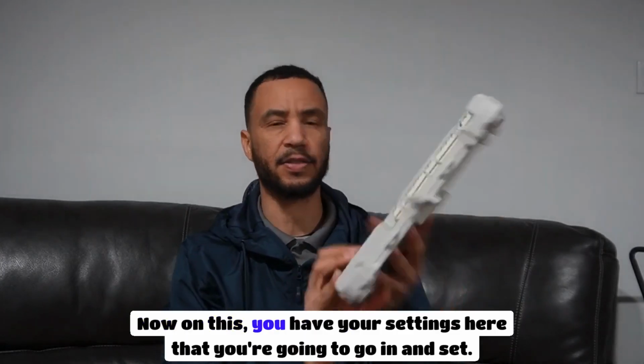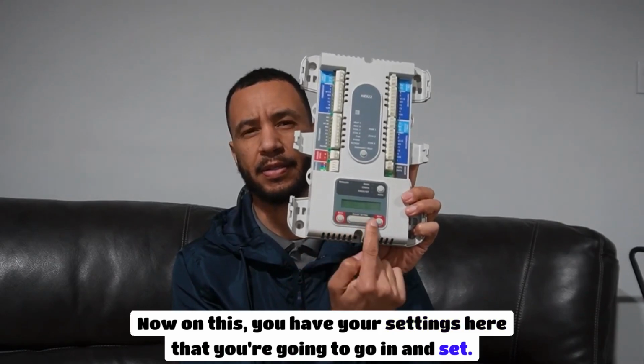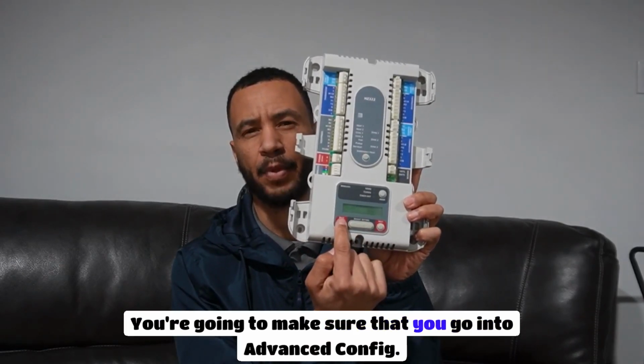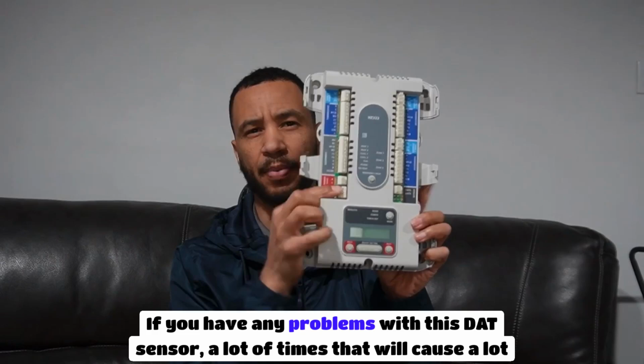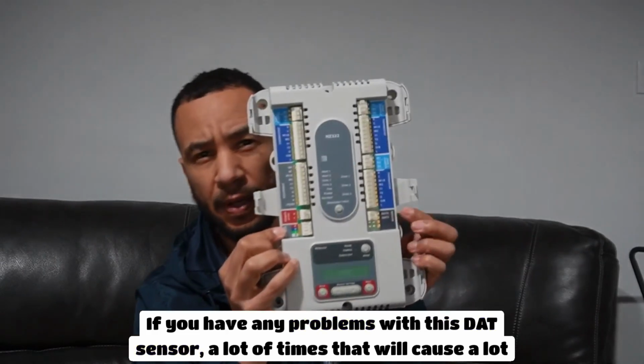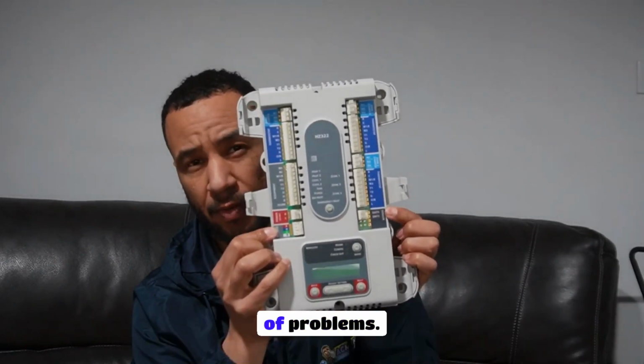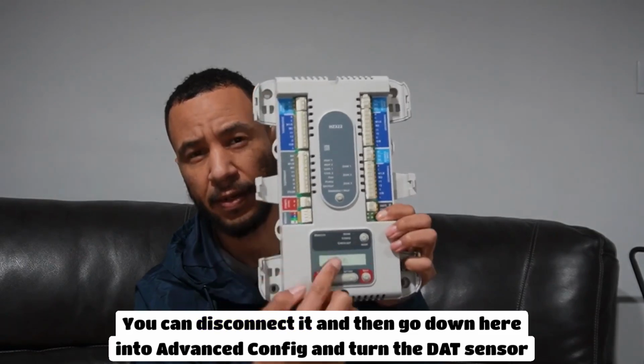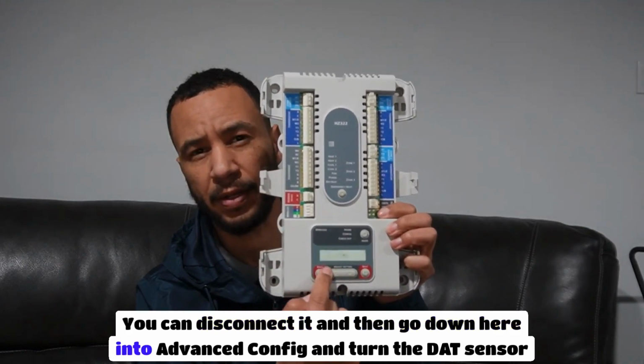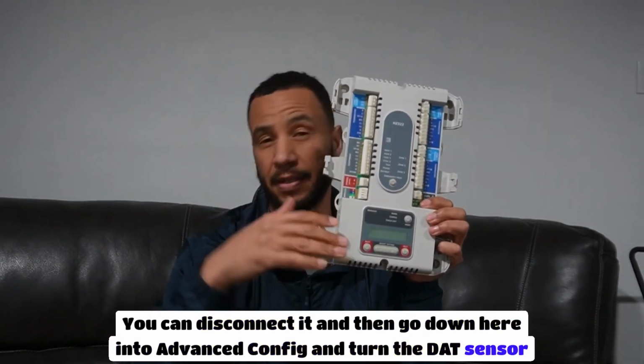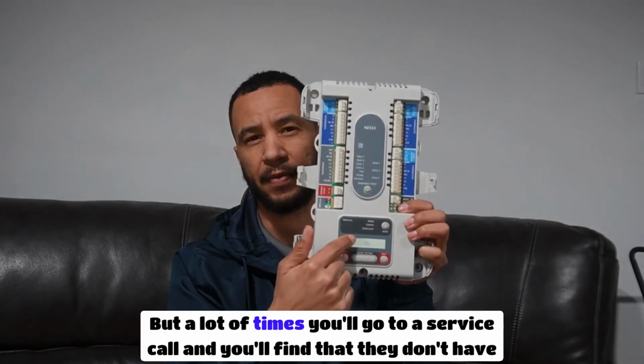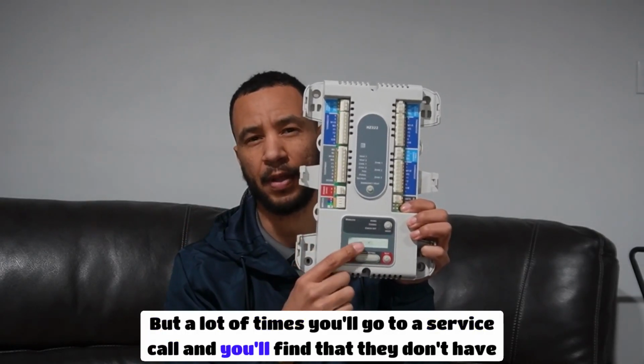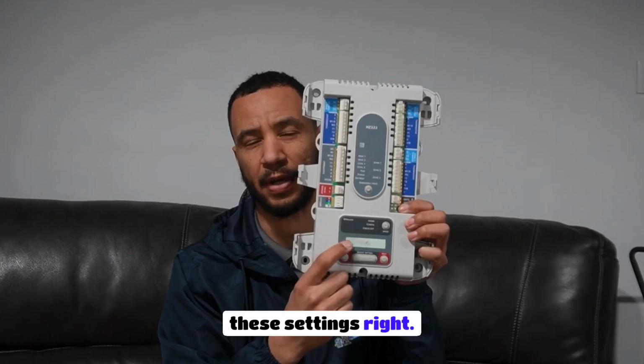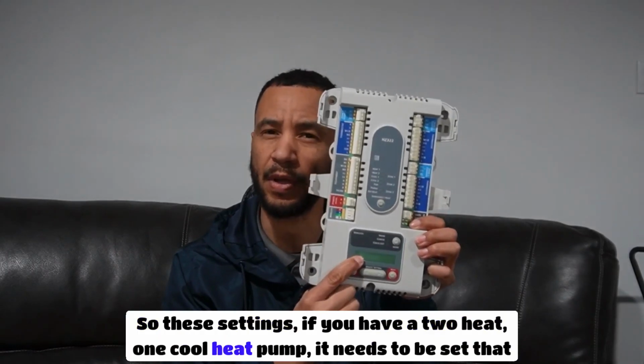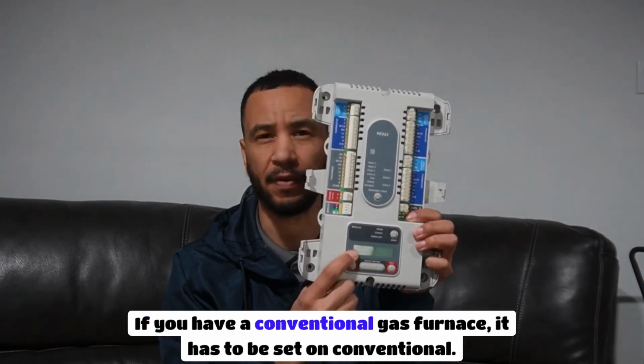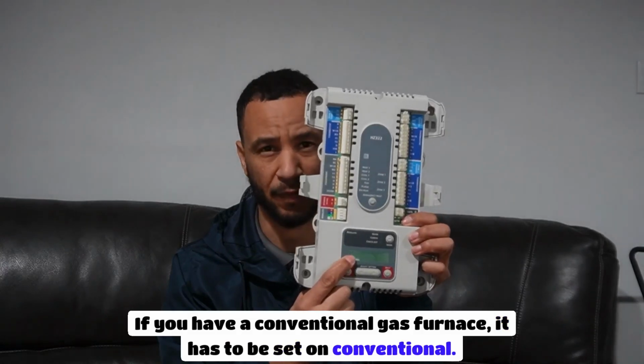Okay, now on this, you have your settings here that you're going to go in and set. You're going to make sure that you go into advanced config. If you have any problems with this DAT sensor, a lot of times that will cause a lot of problems. You can disconnect it and then go down here into advanced config and turn the DAT sensor off. But a lot of times you go to a service call and you'll find that they don't have these settings right. So these settings, if you have a 2 heat, 1 cool heat pump, it needs to be set that way. If you have a conventional gas furnace, it has to be set conventional.